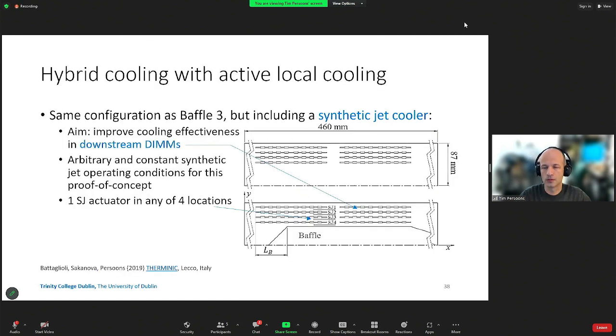If we think back to the same configuration from before, where we have the two DIMM banks, the first one is the upstream bank. This one is typically very well cooled, right? Because it sees the fresh air coming in. But then the second bank has more difficulty in maintaining temperature below the threshold of the components, because of course the air is already preheated when it comes into this second DIMM bank.